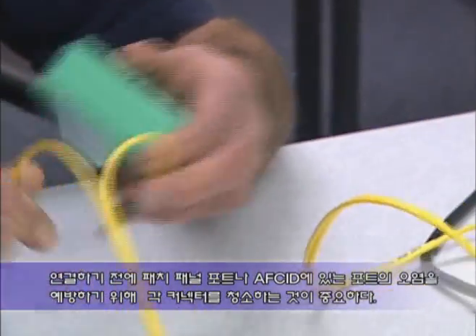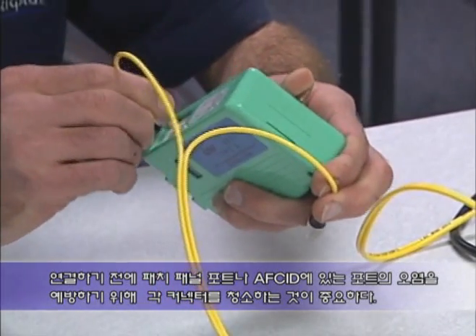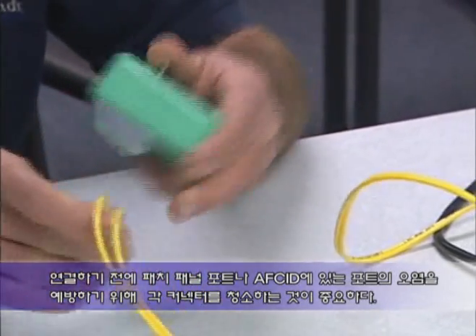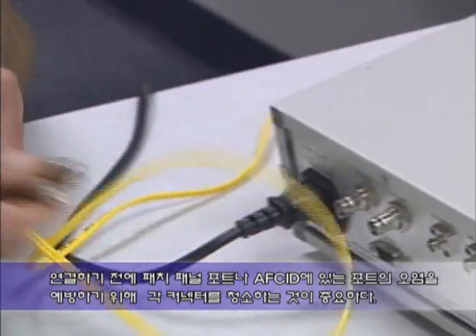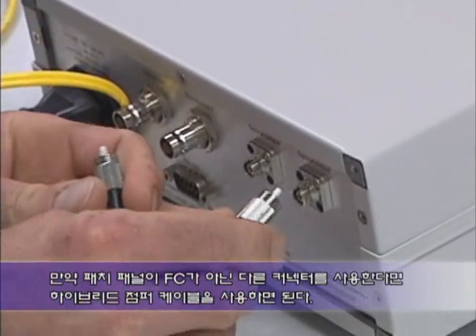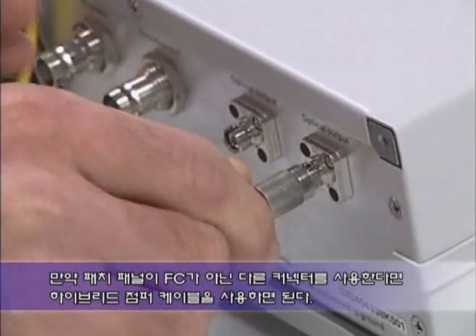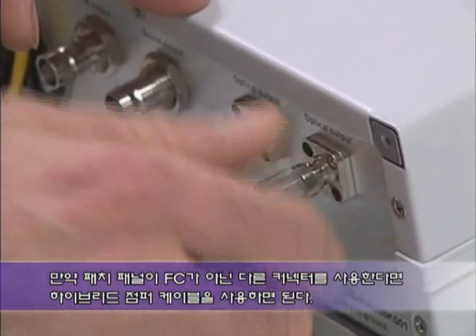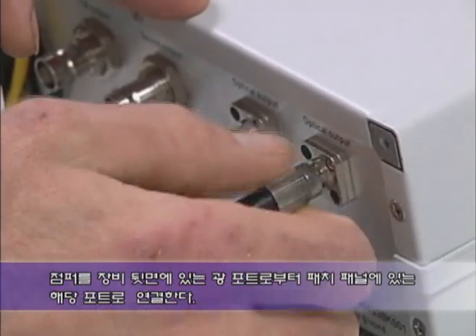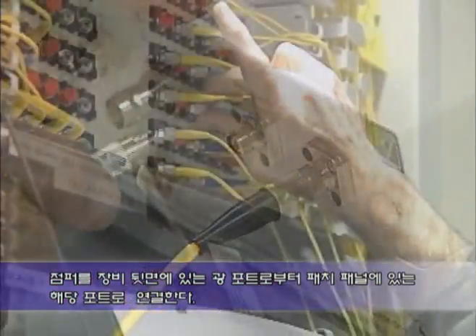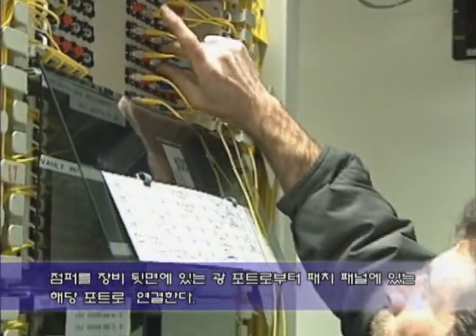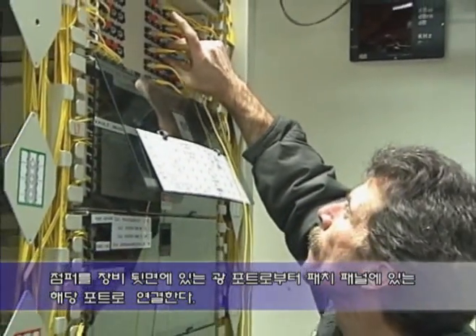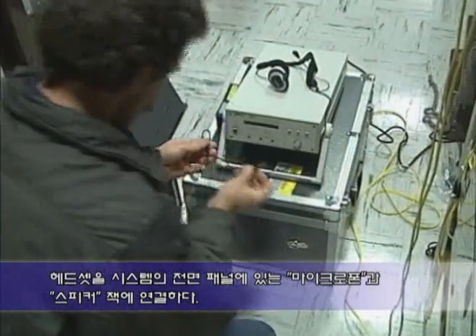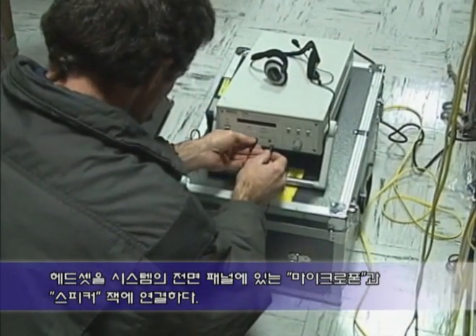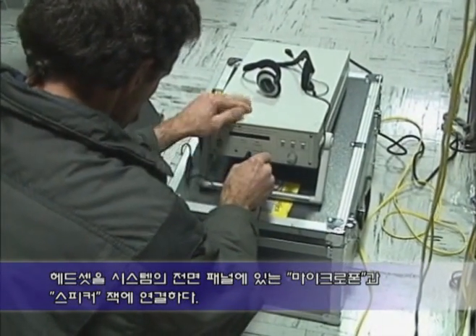Before making any optical connections, it is important to clean each connector plug to prevent contamination of the patch panel ports or the ports on the AFCID. If your patch panel uses connectors other than an FC, you will need to use a set of hybrid jumpers. Connect the jumpers from the optical ports on the rear panel of the instrument to the appropriate ports on the patch panel. Connect the headset to the microphone and speaker jacks on the front panel of the instrument.